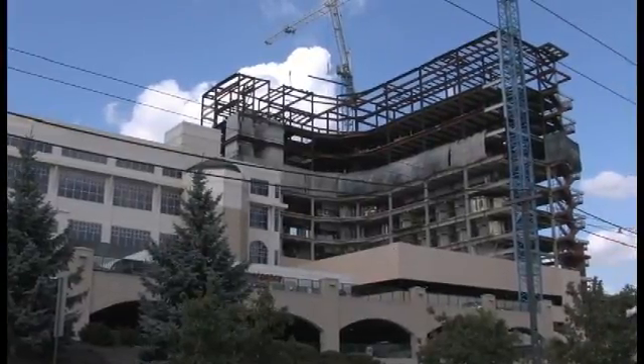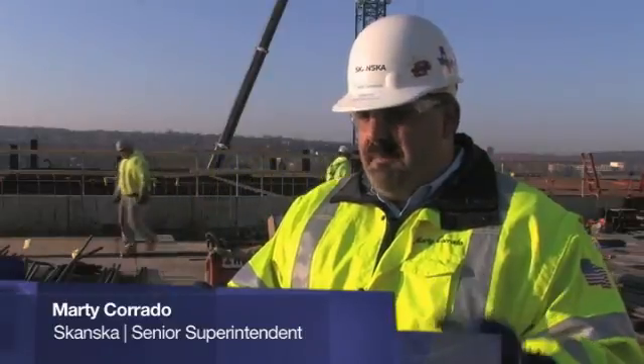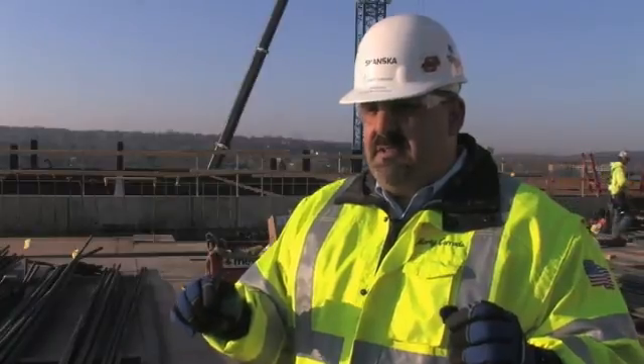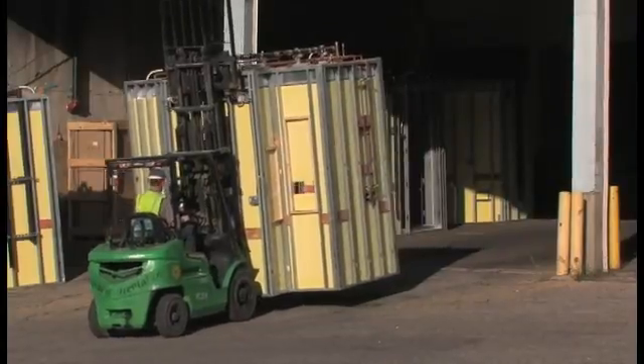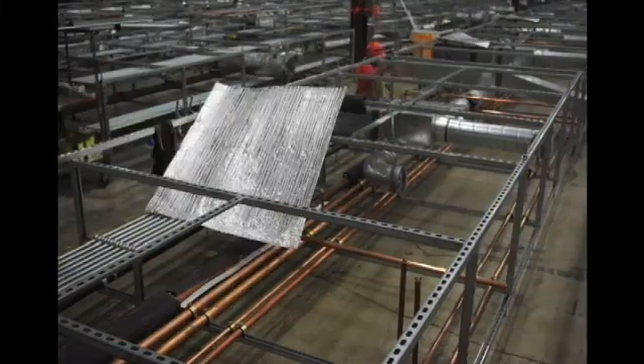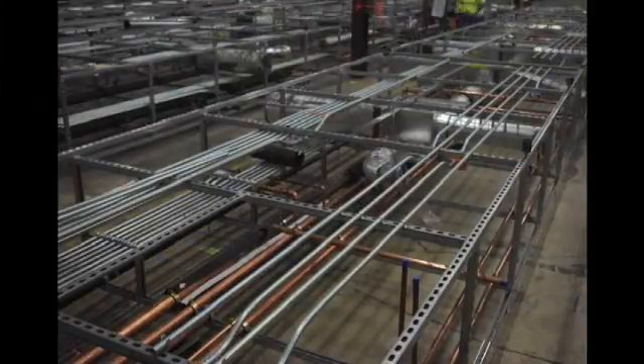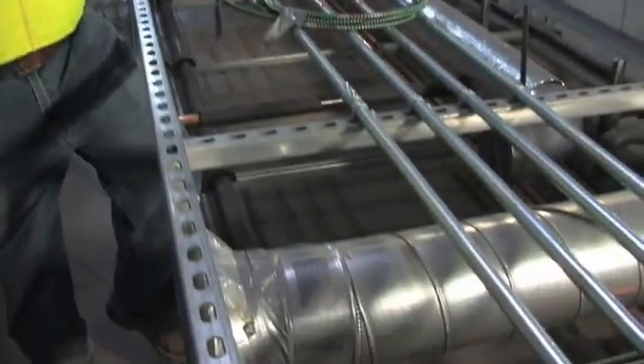This project is different in that we are employing prefabrication of above-ceiling mechanical systems, bathroom pods, and patient headwall systems — and to our knowledge, this is the first time this has been used in the United States on a hospital project. We are at the Miami Valley Prefabrication Warehouse. One of the aspects of prefabrication are these racks, which will contain all the services that go in the hospital: plumbing, med gas, electrical, ductwork — everything will be insulated, labeled, with valve tags, and sheetrock will be on it. The top of the deck is right here, and the ceiling will be below these racks when they're installed.